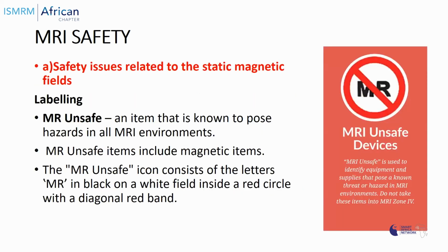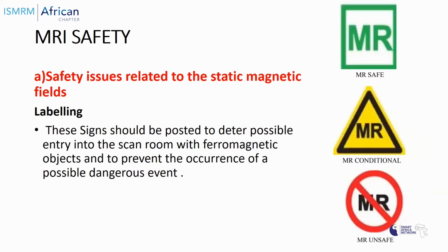Then the last one is the MR unsafe. This is the last labeling type, an item that is known to pose hazards in all MR environments. MR unsafe items include magnetic items. So how does the icon look like? It consists of the letters MR, written in black, on a white background inside a red circle, and then there's a diagonal band across it. When you see this sign, then you know that this device is not MR safe and should not be brought near any MR field. So these are the three types: MR safe, MR conditional, and MR unsafe.